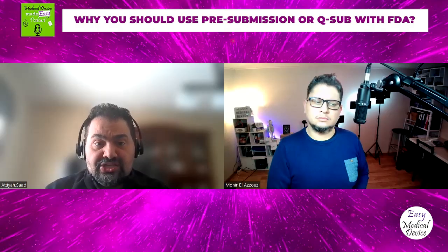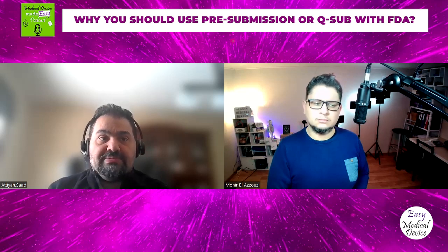And in your submission, 510K or PMA or whatever it might be, my recommendation, better yet, would be to document what was discussed and what was agreed upon. This helps the reviewer in that process. Again, the reviewer may find additional topics, and they have to address those. Companies do have to address those topics.